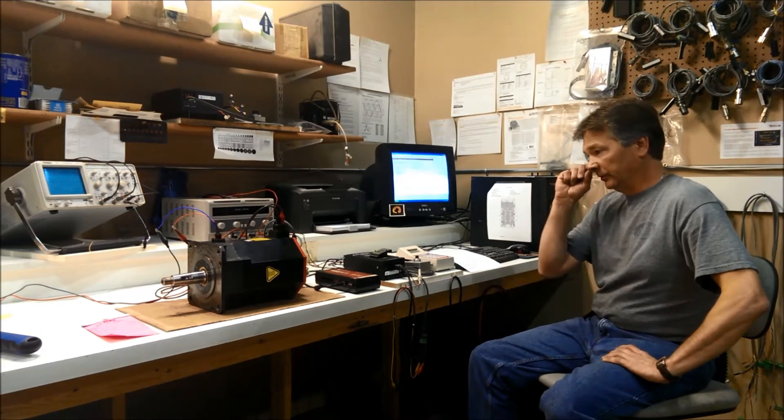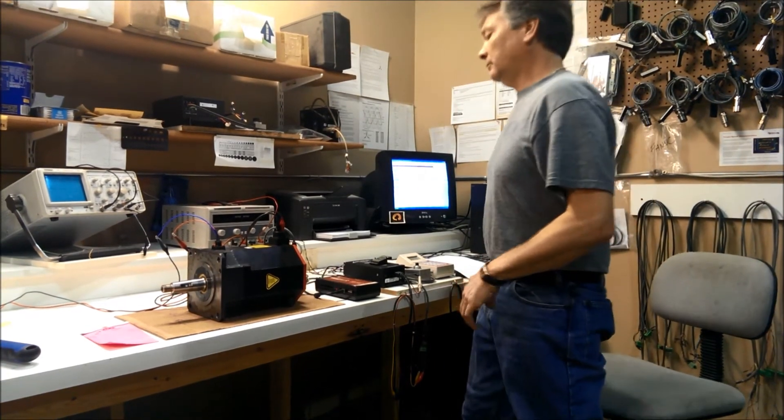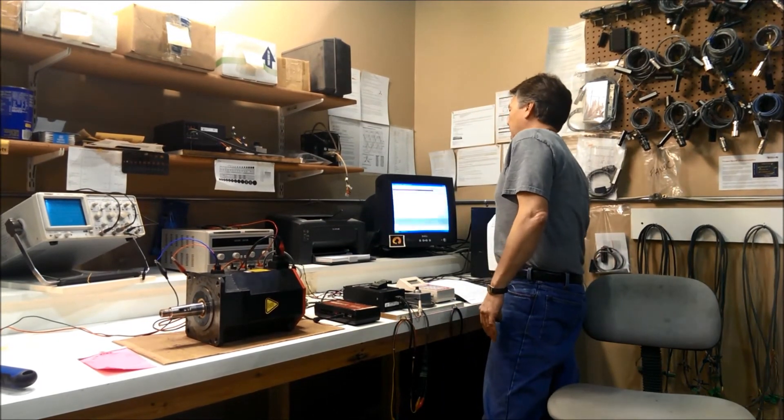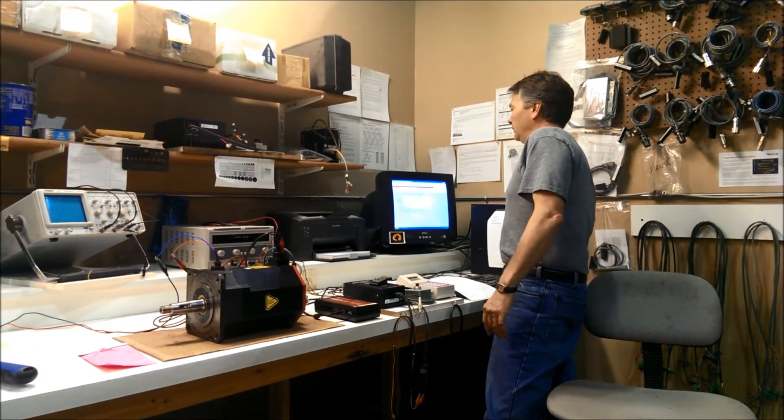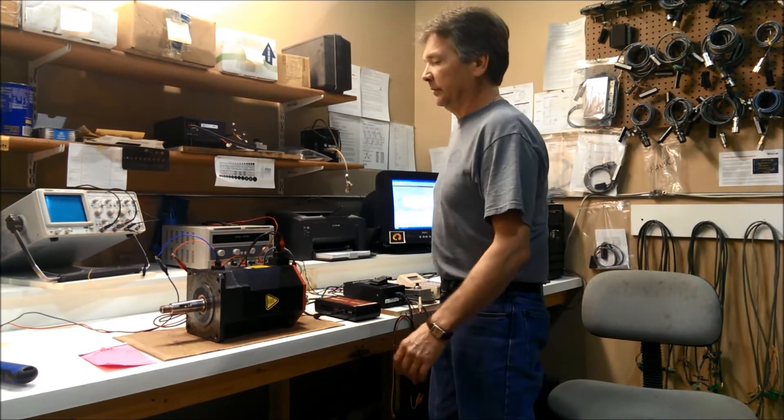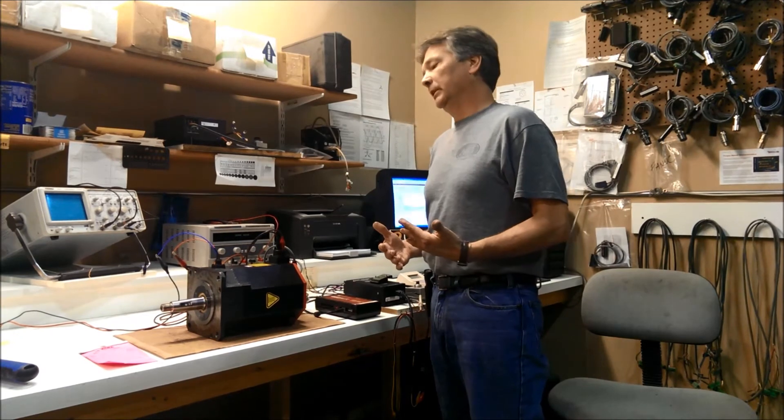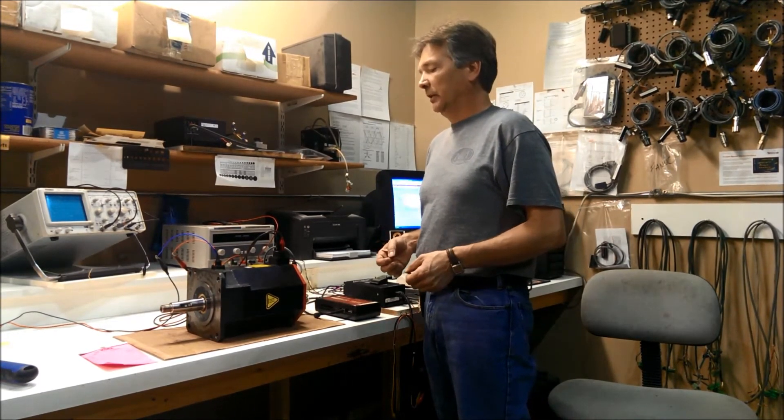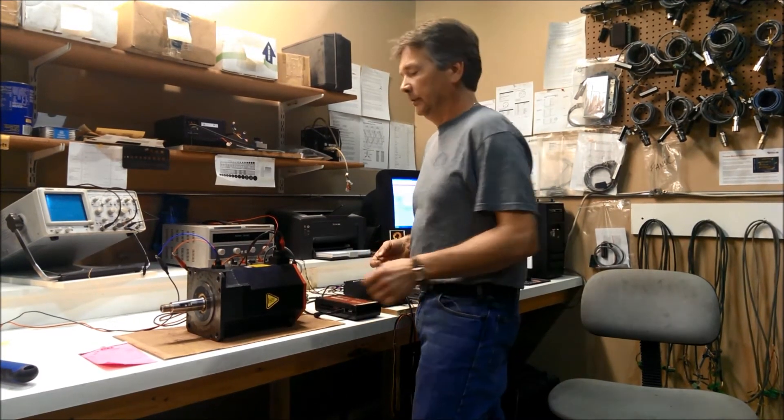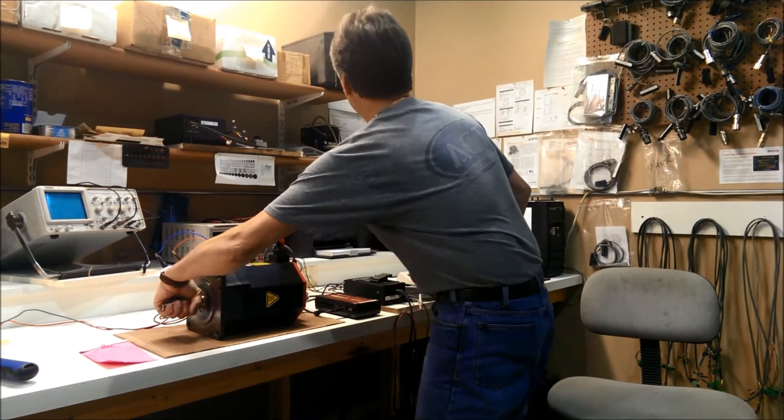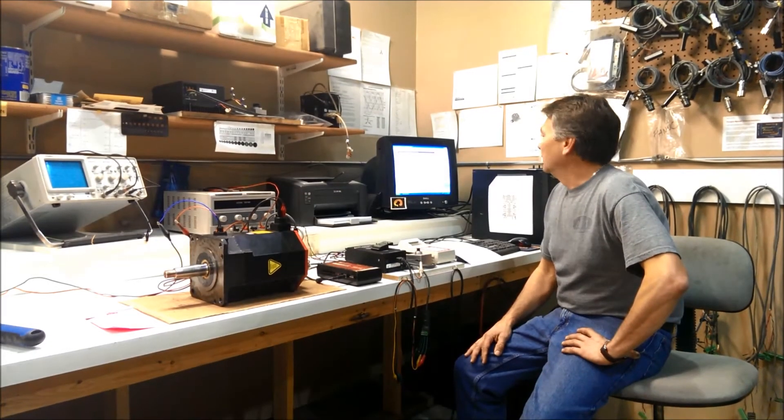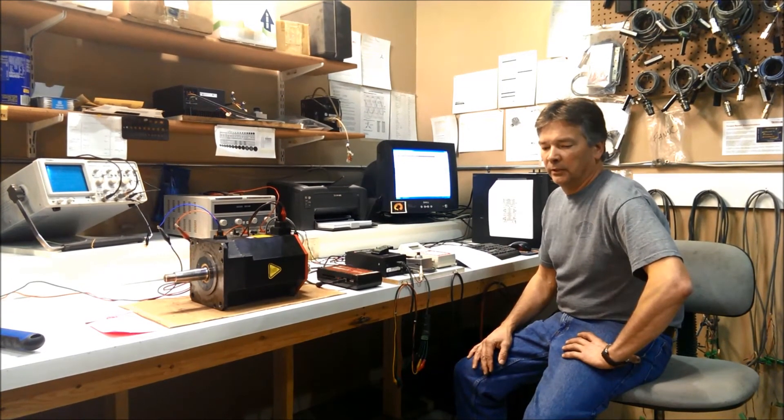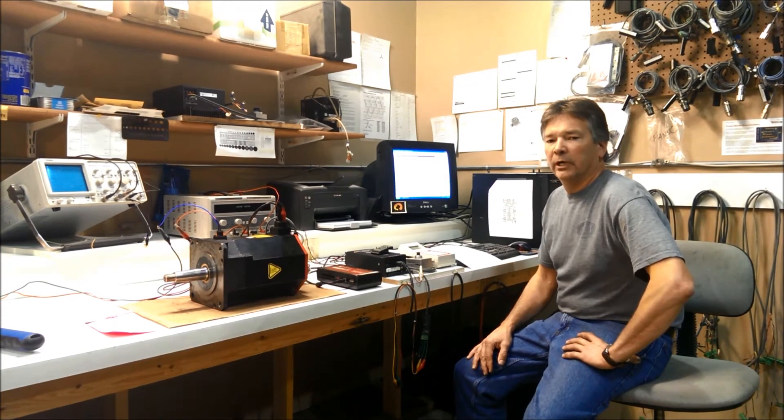One of the first things that we'll do when we're testing with the Mitchell equipment is we'll hook up the encoder and then we'll do what we call a count test, which is probably the most important test that we do on the feedback devices. It verifies that the feedback device is actually counting properly, which is integral to making sure that the motor operates and rotates properly. So we'll turn the shaft of the motor to determine whether or not the encoder is operating properly. We'll do a few times, four revolutions, and continuous count tests where we rotate the encoder and continue to check the encoder to make sure that it's counting properly.